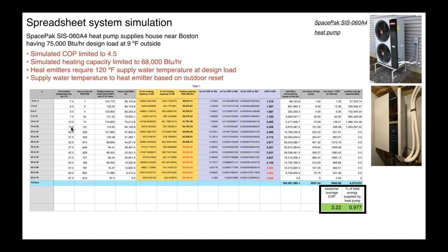So over here, you'll see our bin temperatures, our average temperature and the number of hours. And underlying these cells in the spreadsheet are those formulas. So we're basically just doing a lot of calculations that, yeah, we could do by hand if we had a week, but we're doing it almost instantaneously by building the spreadsheet. Now, you want to be careful when you do models, because remember, these polynomial functions are continuous functions. And when you get into the far regions of your operating range, sometimes they can grossly overpredict or underpredict what's happening. So just to try to keep this thing realistic, I limited the COP to no higher than 4.5. You can see over here, this is where the heat pump's COP is being calculated, and it doesn't go above 4.5.